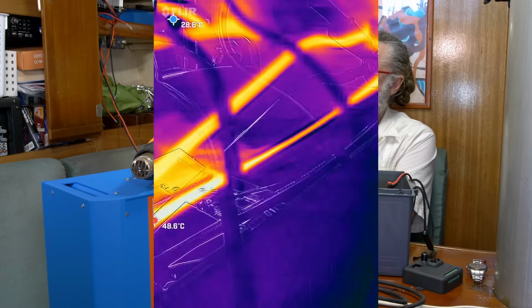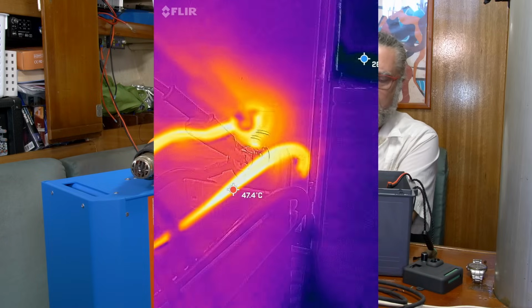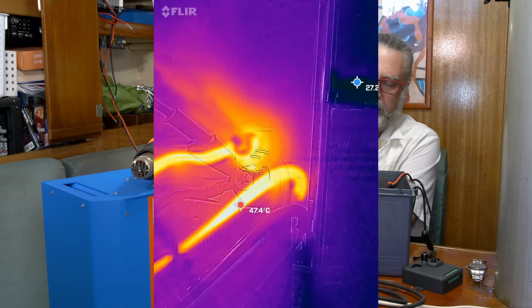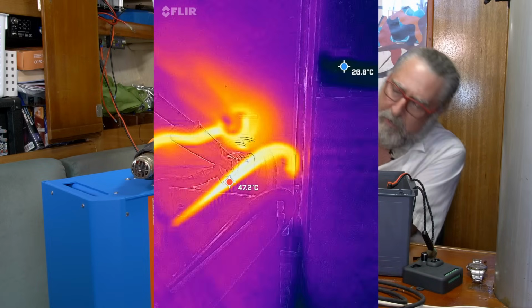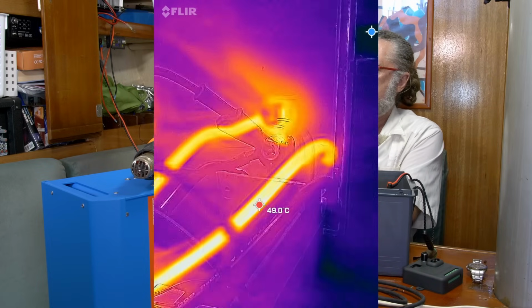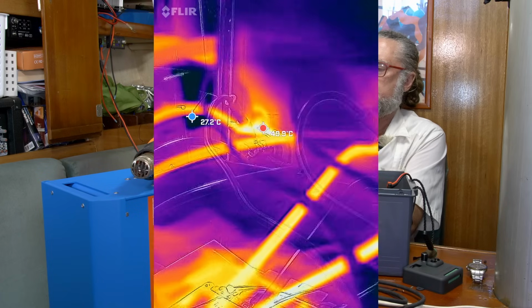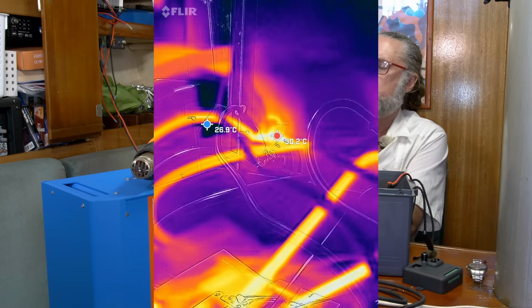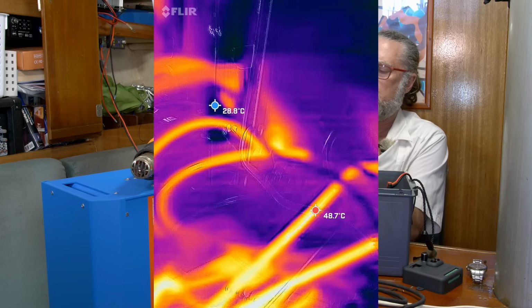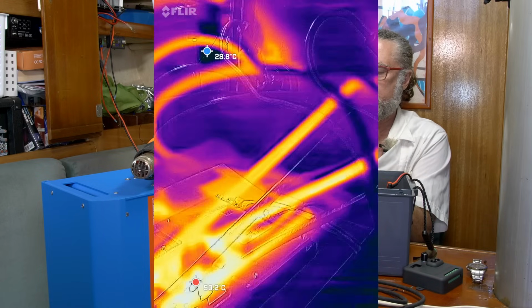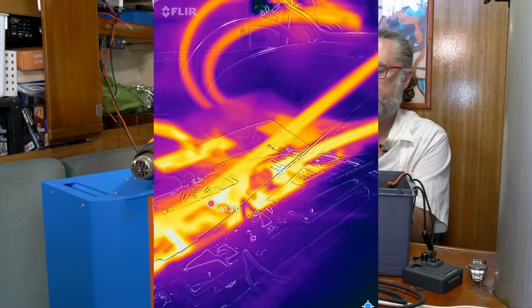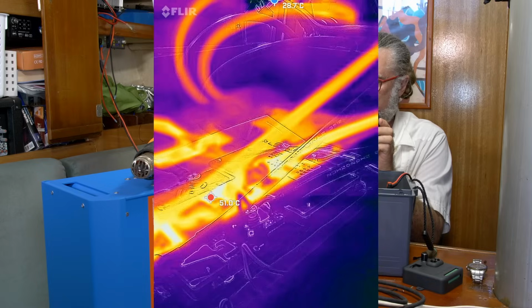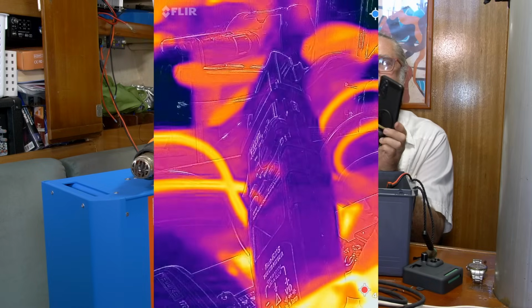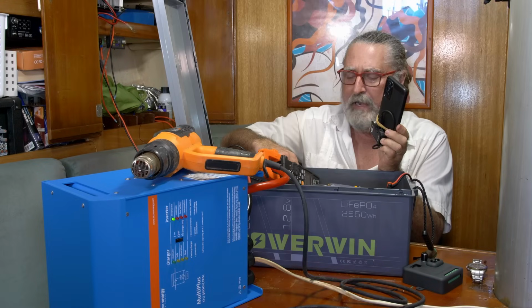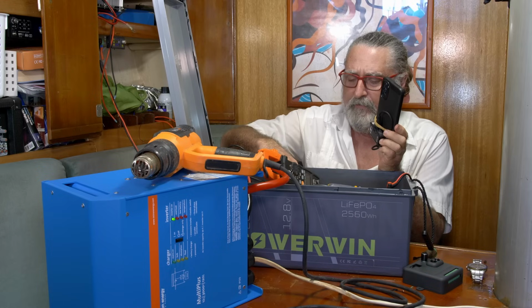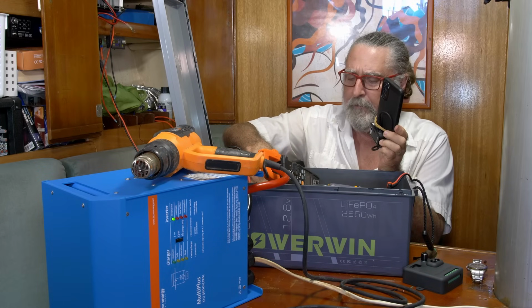And what do we have? After 15 minutes, it's still at 12.8, 12.78 volts. It's been running 100 amps the whole time. There's a 48-degree spot. There's one 50-degree spot right here, but that's maybe not tight enough on the contact. Oh, here we go, the hottest spot is 51 degrees, and yeah, it's warm. But I can hold my hand right on it. It's not that hot at all.